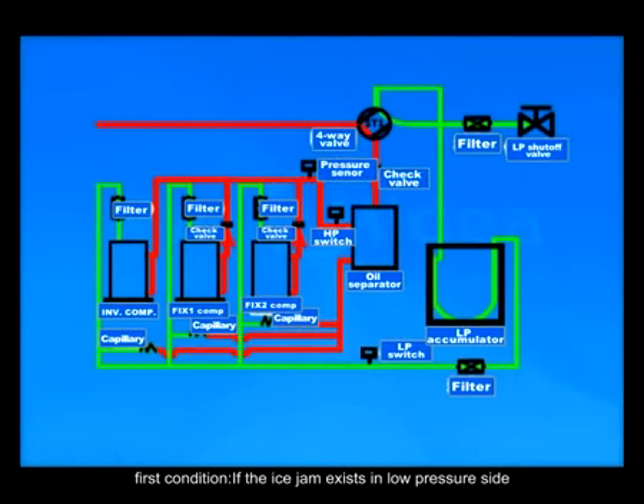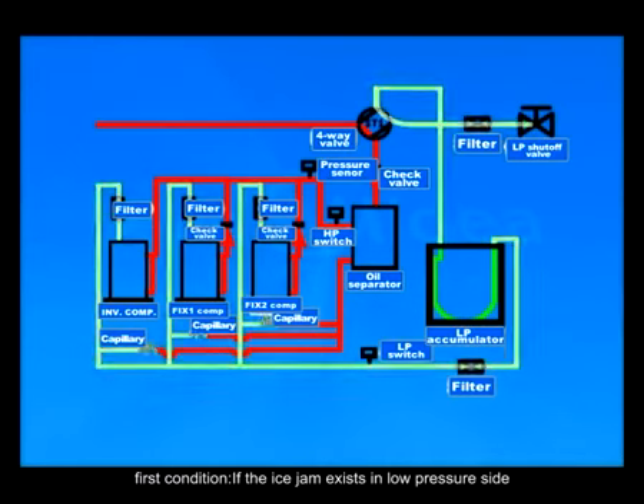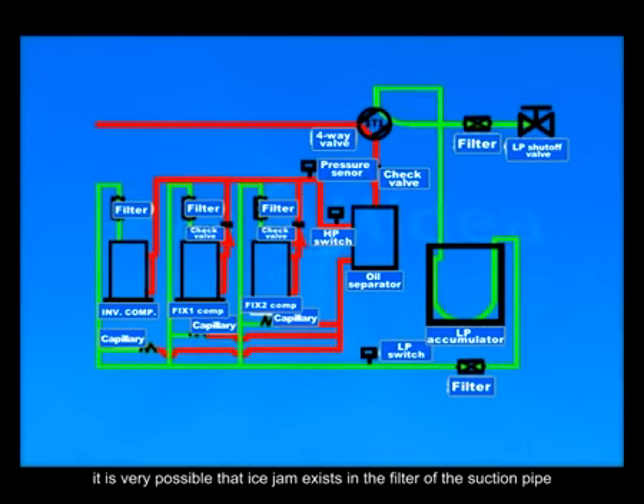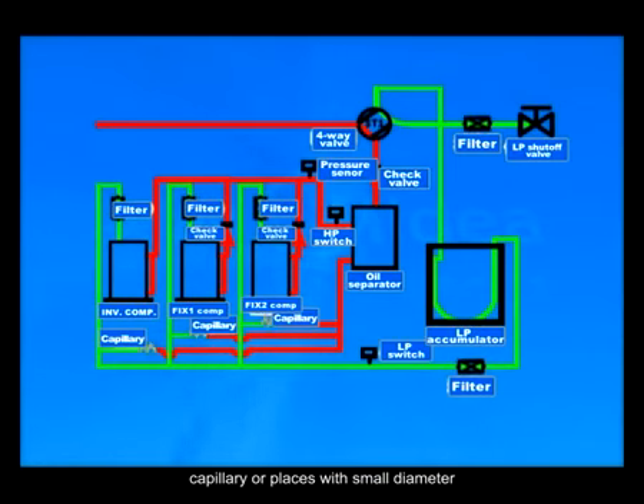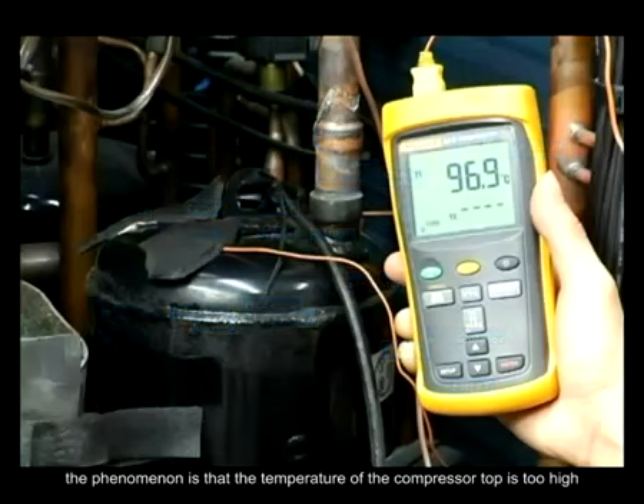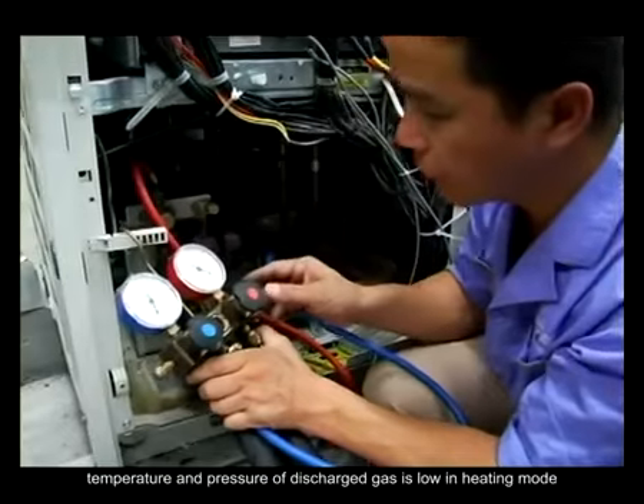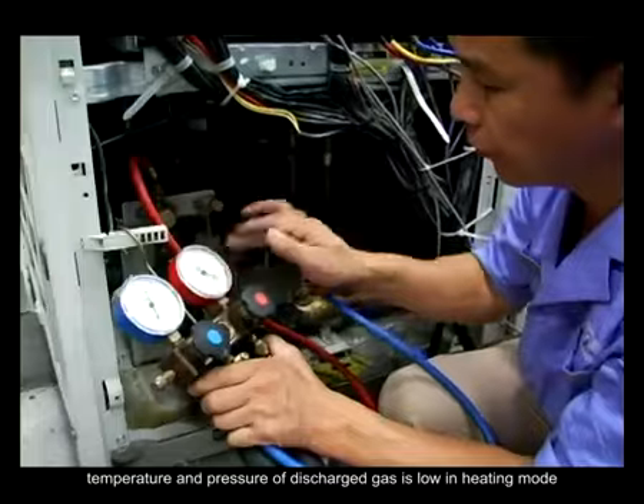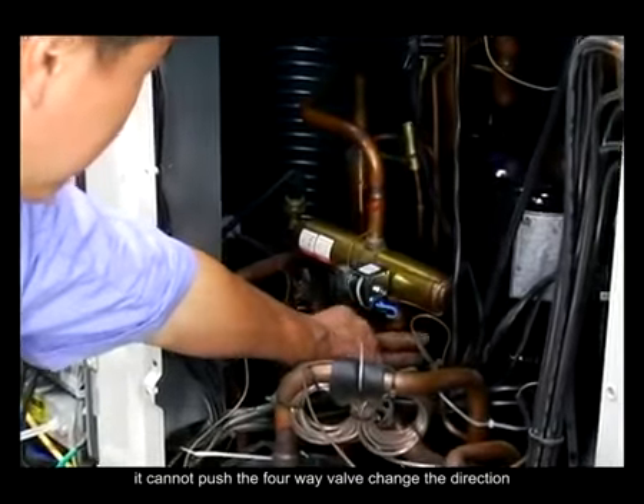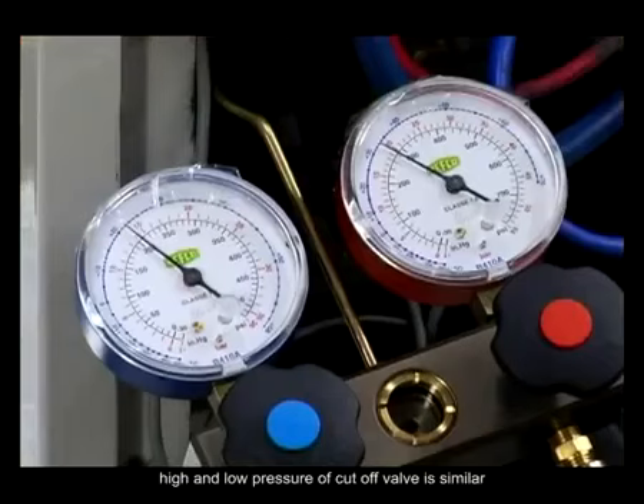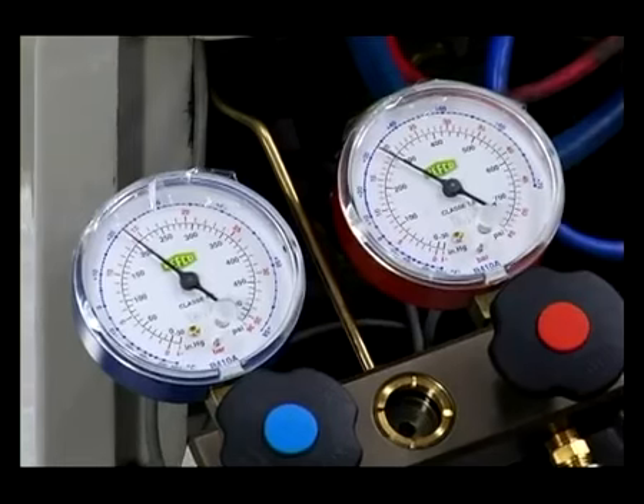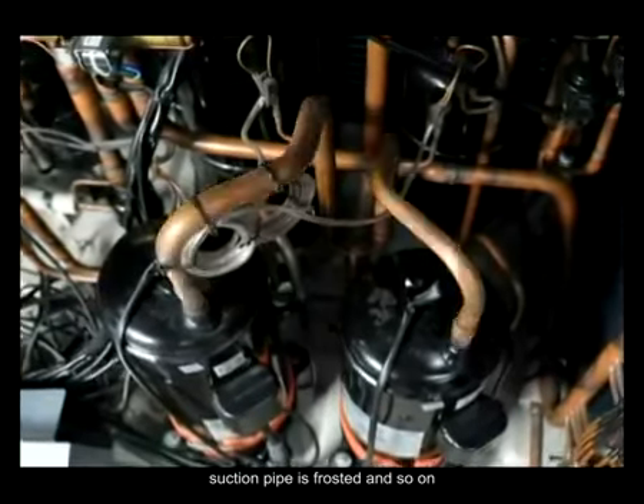First condition. If the ice jam exists in the low pressure side, it is very possible that ice jam exists in the filter of the suction pipe, capillary, or places with small diameter. The phenomenon is that the temperature of the compressor top is too high. Temperature and pressure of discharged gas is low. In heating mode, it cannot push the four-way valve change the direction. High and low pressure of cutoff valve is similar. Suction pipe is frosted, and so on.